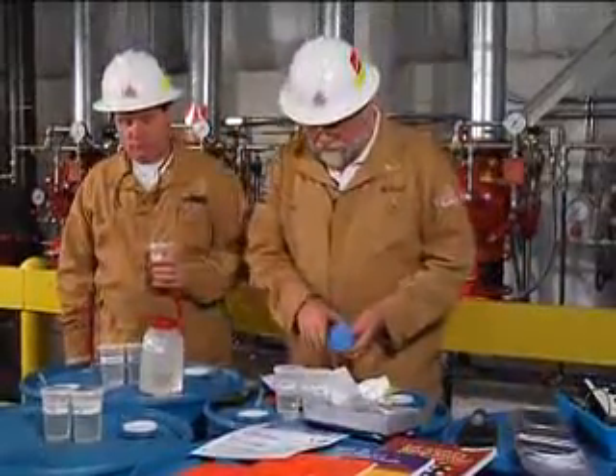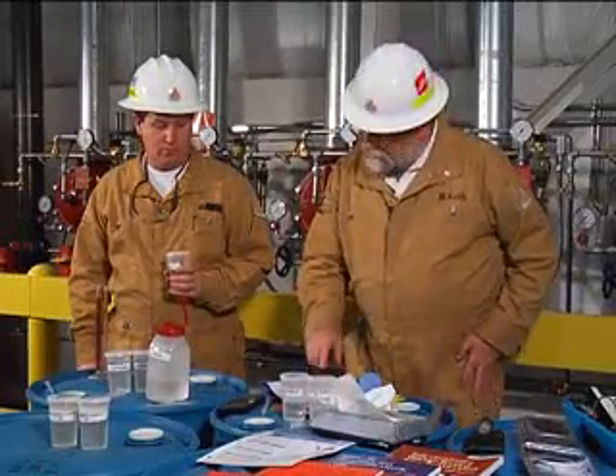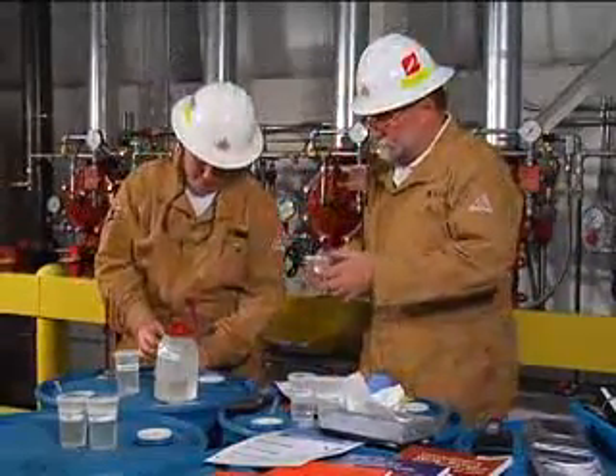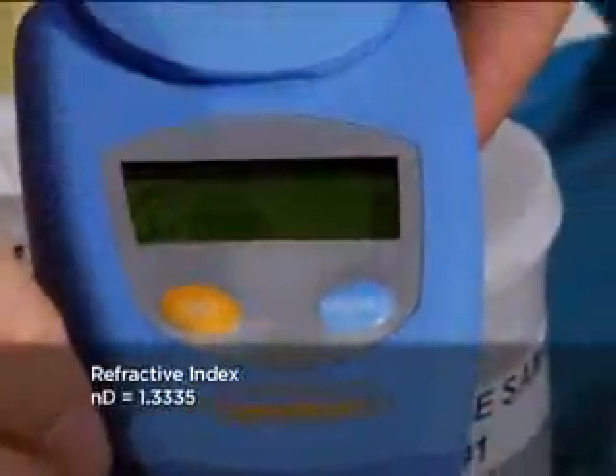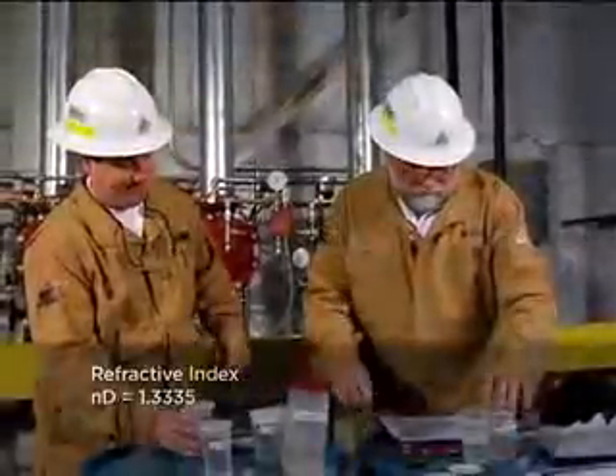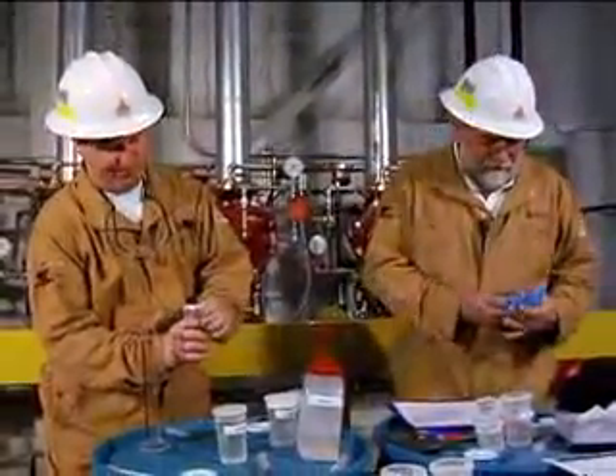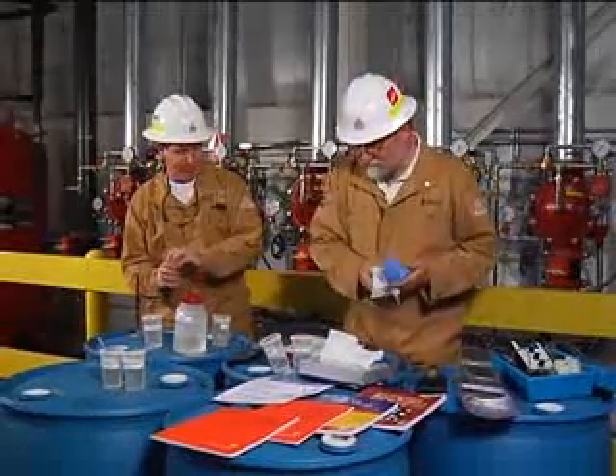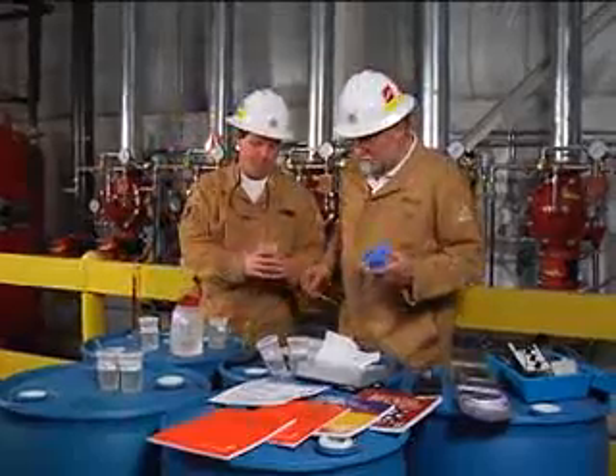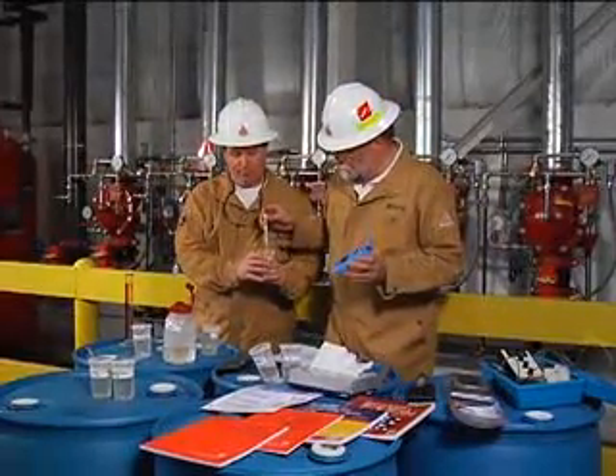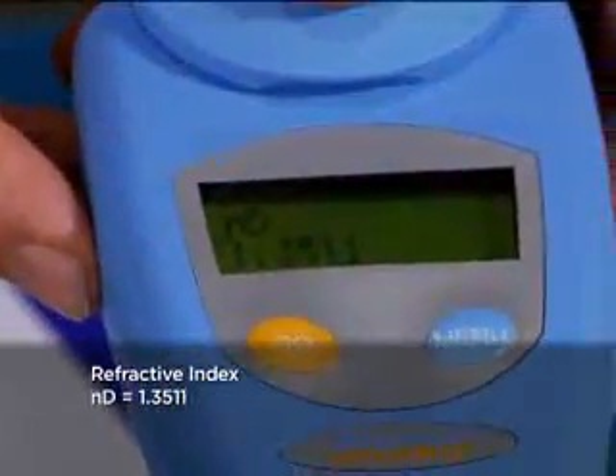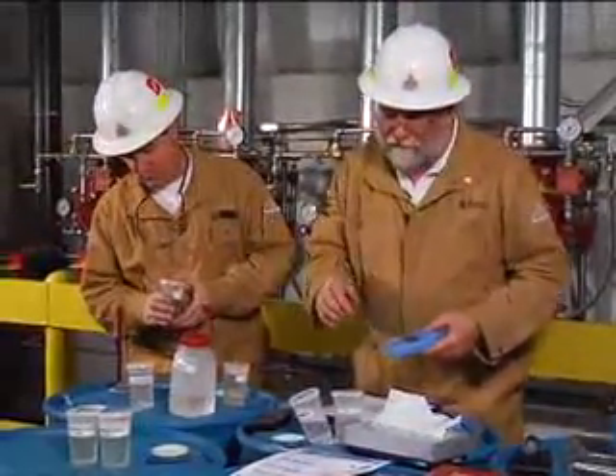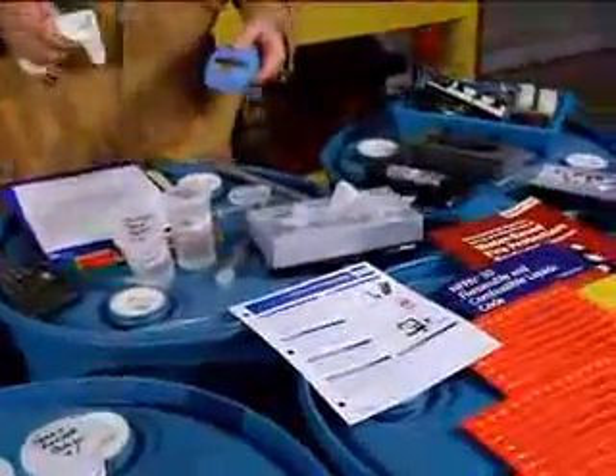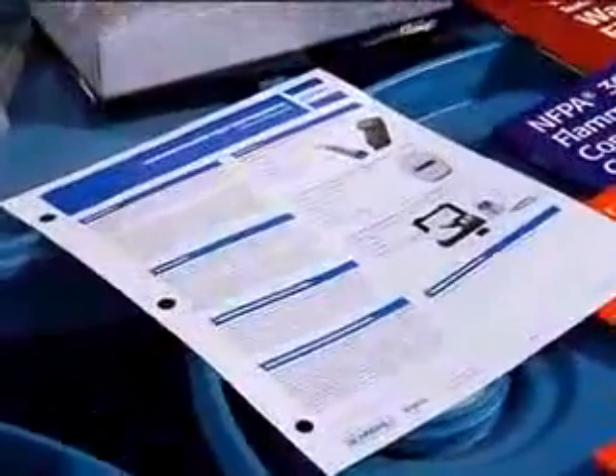And if there are any points that you had which were suspicious to you, you could certainly go back and retest them. And I'm going to do that. I'm going to test the 3% premix standard one more time. And I do. I'm getting 1.3335. The last thing I'll do on the refractometer is take a reading of what the refractive index is for the pure undiluted foam concentrate. This is giving us a reading of 1.3511. And that would be a typical refractive index reading of the concentrate as indicated on the Ansul technical data sheet for the type of foam concentrate that's charged in the system.